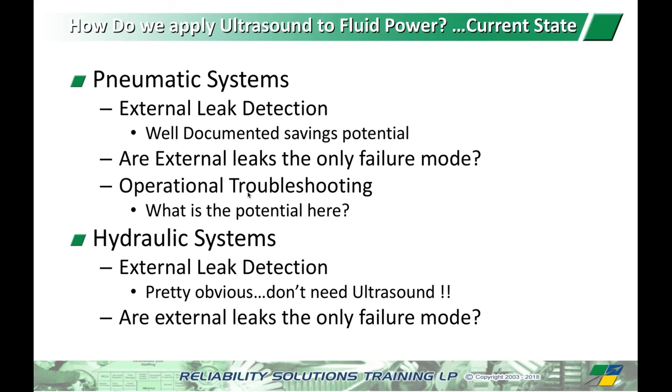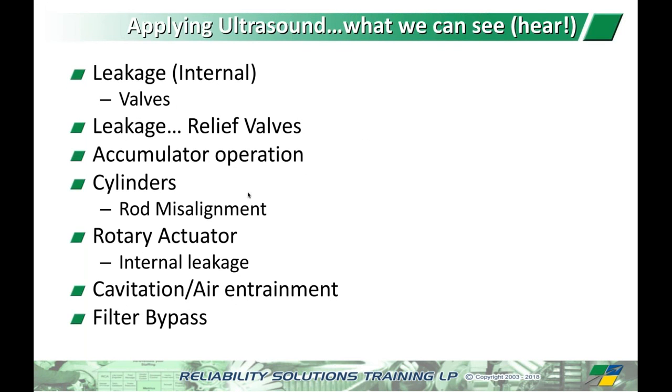And so after that, they actually instigated a practice where they trained the operators to use, and I think they were UE 100s at the time, it was a long time ago now. They were just using UE 100s. And so when they had a misfire or something wasn't working right, they'd go listen to this and they'd pick out the right solenoid and save them a bunch of money. So, in terms of operational troubleshooting, that's a pretty useful tool. There's lots of ways we can use it.